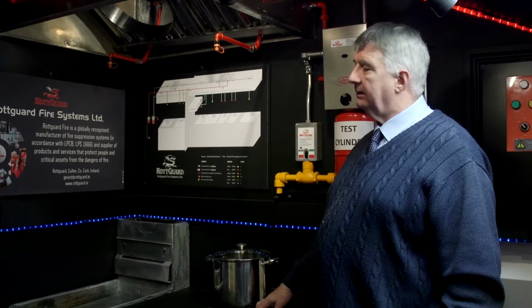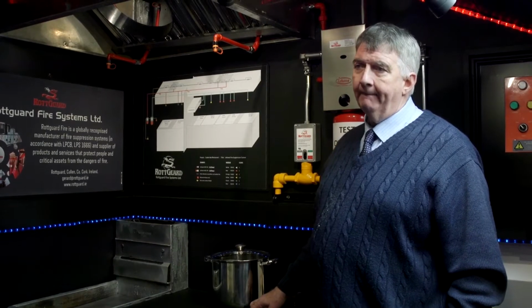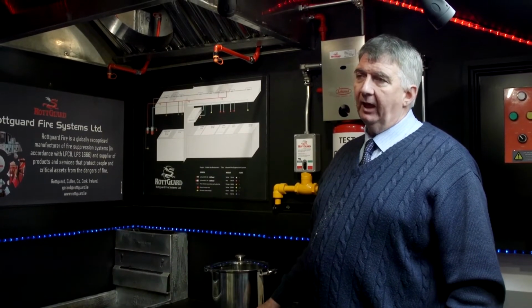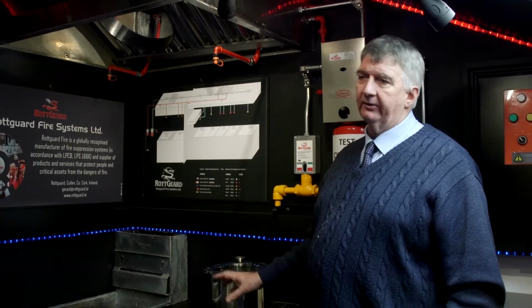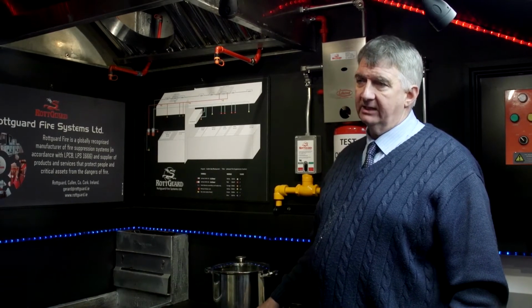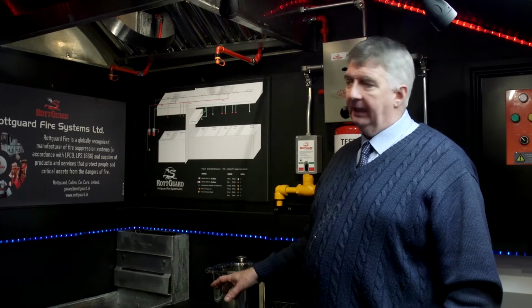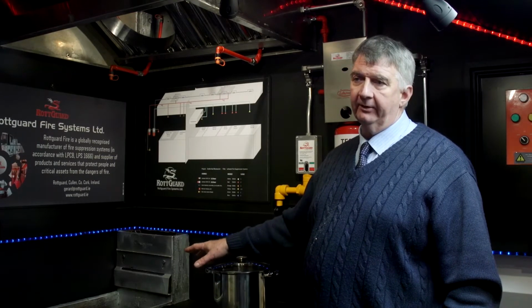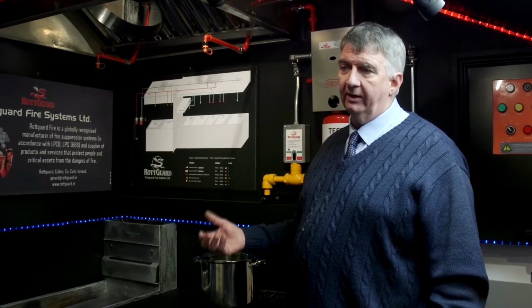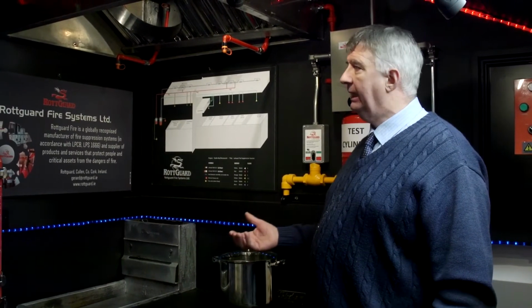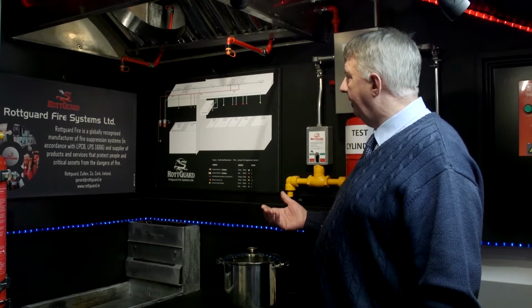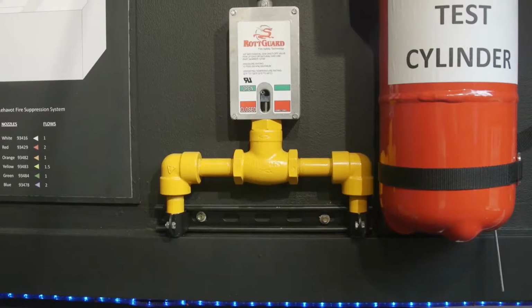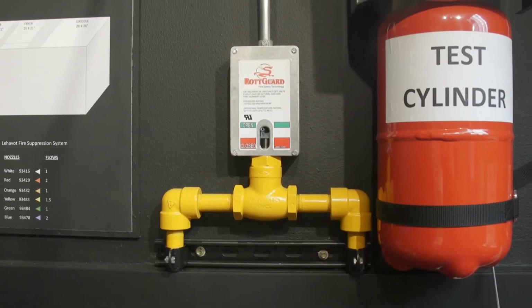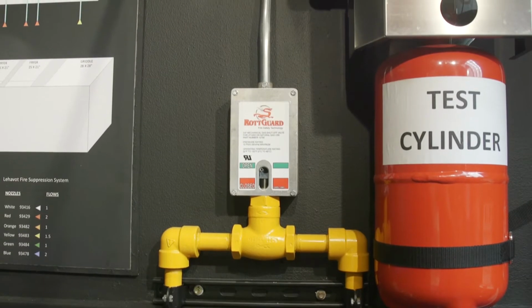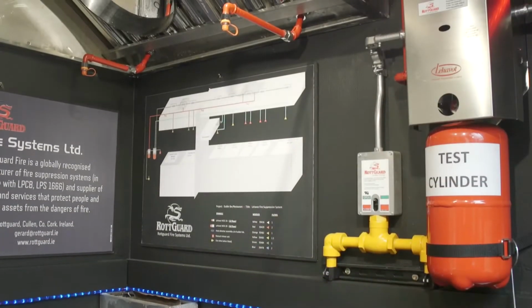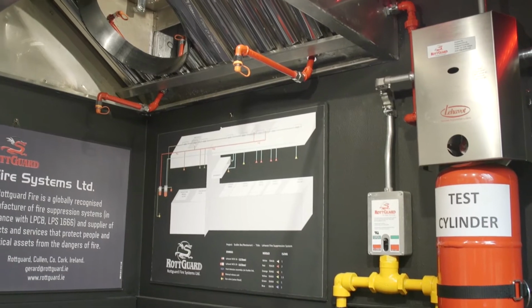The wet chemical extinguishes fire by cooling, and it creates a soap-like froth referred to as saponification on top of the burning oil in something like a deep fat fryer. Again, we rely on photographs, if not a drawing supplied of the actual kitchen, and we determine how many cylinders, the size of the cylinders, which come in different sizes, and we produce a design drawing like this showing the different color-coded nozzles and where they should be.